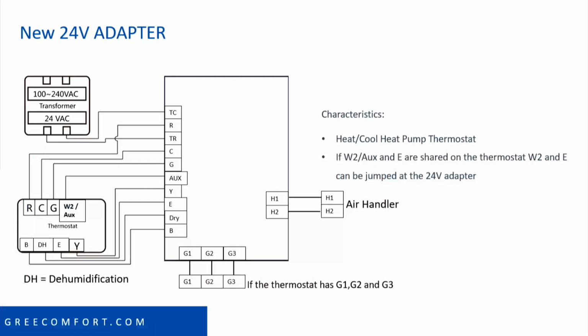We wanted to give a little more detail about the dehumidification function on the 24-volt adapter. So if we can share the slide and talk about how that works. James, from the 24-volt adapter, we're just hooking that to the thermostat on the DH terminal, correct? That's correct. When 24 volts is detected on the dehumidification terminal, it will slow down the fan speed to basically medium fan speed, which is about 2/3 of high speed. So it's important that we set our static pressure to match our ductwork so that we can dehumidify properly.